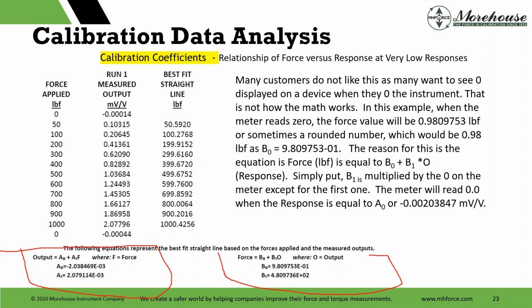Here's coefficients. So we draw this line, millivolt per volt calibration, and then we draw the best fit straight line. So if somebody were to put those millivolt values in a meter, they could expect to maybe match this. They're going to have an additional error component from the meter. This is about the best it's going to get unless they start using a higher order fit. And typically with a 10-point calibration, just drawing a straight line is good enough.